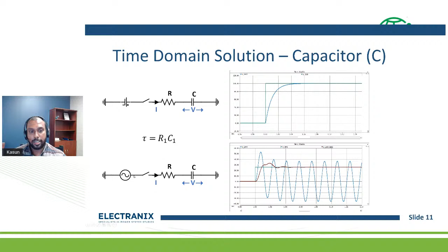Here are some examples of studies that require EMT. Electromagnetic transients are required to model lightning and switching overvoltage studies, like assuming a lightning strike on a transmission line, where we need to see how the voltage increases and whether the BIL is enough to stop restriking. We need to model all these details in the EMT domain to see these fine details. This is one of the high frequency studies especially done in EMT.